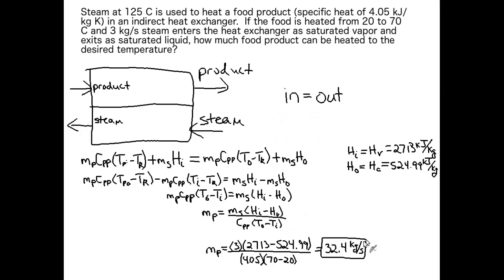And looking at the specific heat of our product, it's pretty high—it's close to water—but it's not that big in comparison to how much heat we are getting from that phase change in steam. So this is actually a realistic amount of product that could be heated with three kilograms per second of steam. So when you have steam in your energy balance, a little really does go a long way.